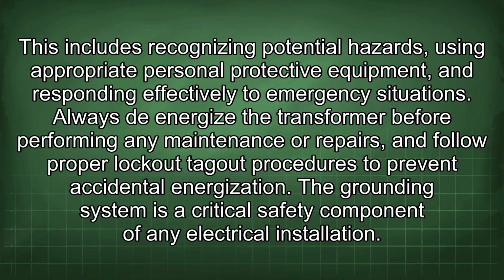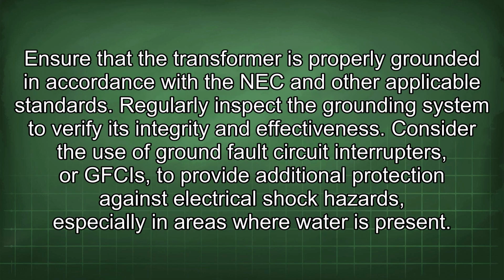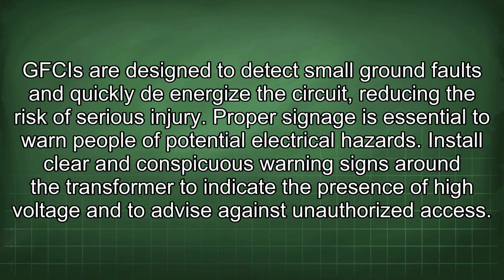The grounding system is a critical safety component of any electrical installation. Ensure that the transformer is properly grounded in accordance with the NEC and other applicable standards. Regularly inspect the grounding system to verify its integrity and effectiveness. Consider the use of ground fault circuit interrupters, or GFCIs, to provide additional protection against electrical shock hazards, especially in areas where water is present. GFCIs are designed to detect small ground faults and quickly de-energize the circuit, reducing the risk of serious injury.